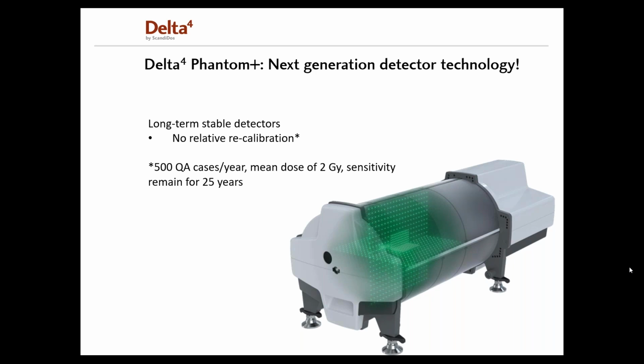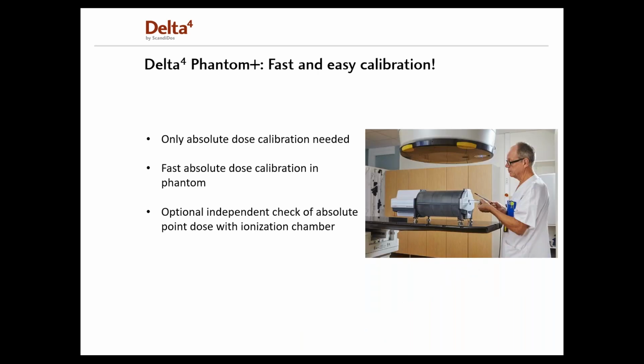Regulatory requirements may be different for every country, of course, and one might need to do relative recalibration annually. And of course, you can do that, but it's good to know also that the calibration procedure is improved and is much easier and is done in the measurement Phantom and does not require any disassembly of the Phantom. The cylindrical Phantom also has inserts for different ionization chambers. This allows the absolute dose to be verified with an ionization chamber directly in the same Phantom. It also allows the absolute calibration to be performed without any disassembly of the Phantom, and this is convenient when you want to do calibrations on different accelerators. Inserts are available for common cylindrical chambers like the Farmer, Semiflex, and so on. And also the system offers independent check of absolute point dose.